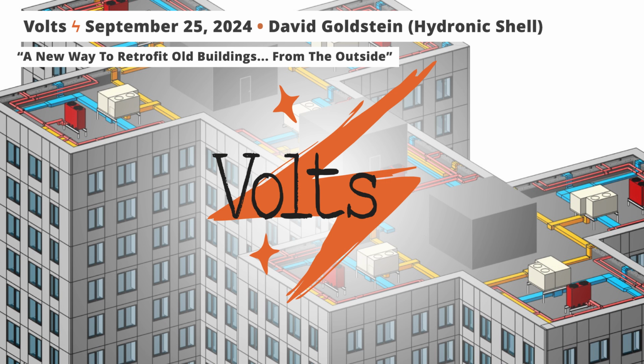That's right. So we have that distribution, the ductwork and the piping running in the facade, and the terminal unit is essentially plugging into that distribution network. So at the window, you have this terminal unit that plugs into the piping and into that ductwork to be able to deliver that heating, cooling, and ventilation into the space. Yeah, this is an area where I feel like the audio nature of this medium is a disadvantage. It's very helpful to look at a picture of this.